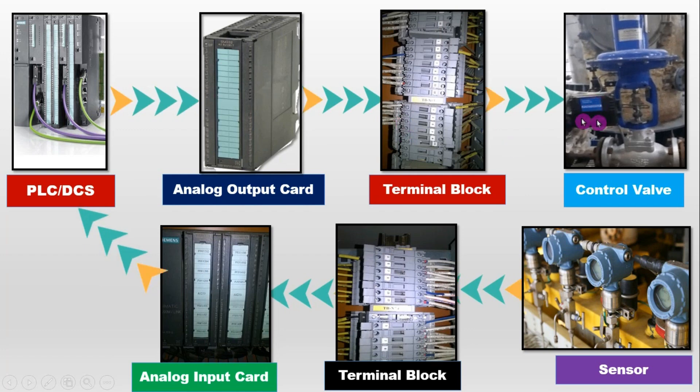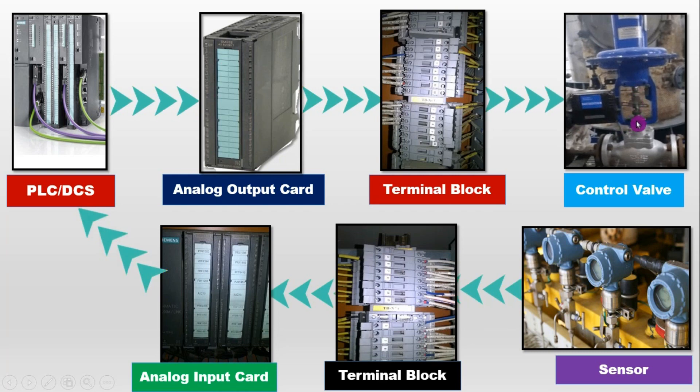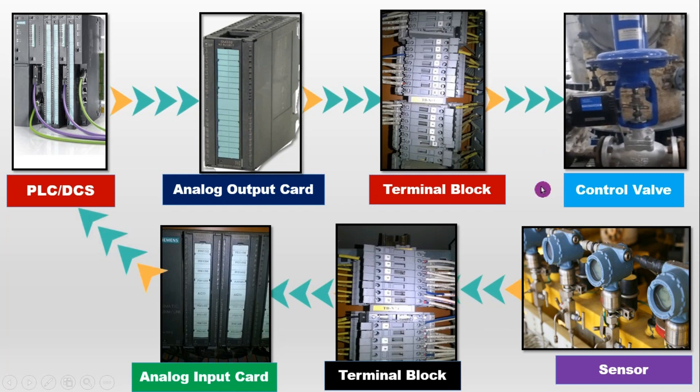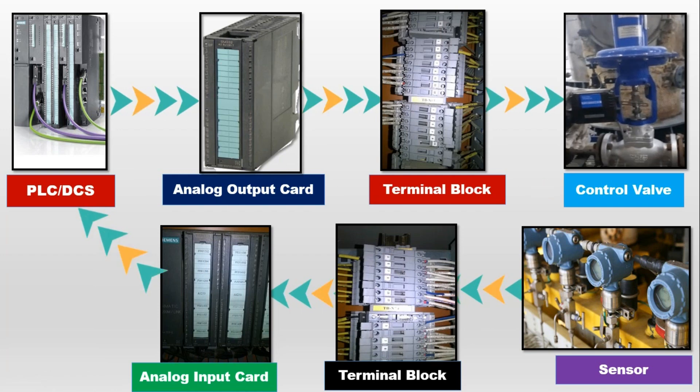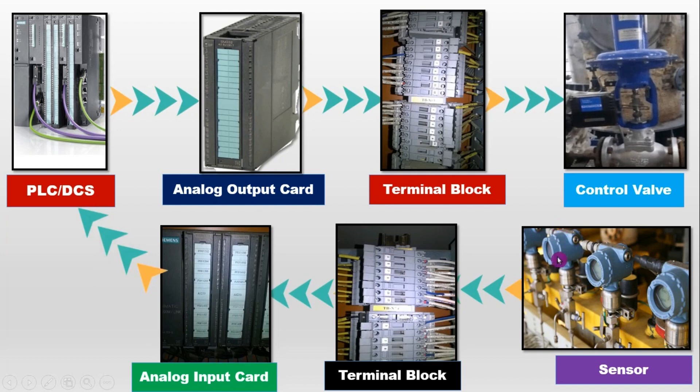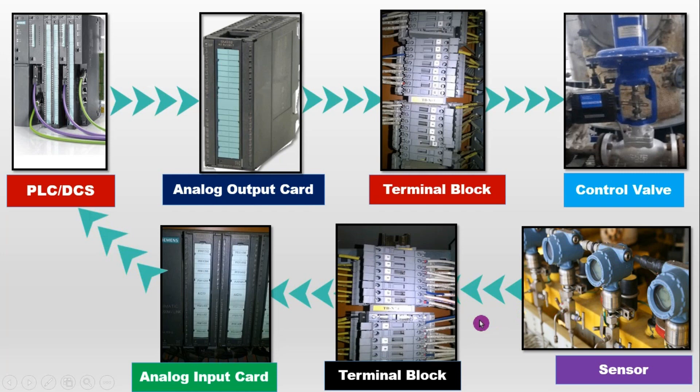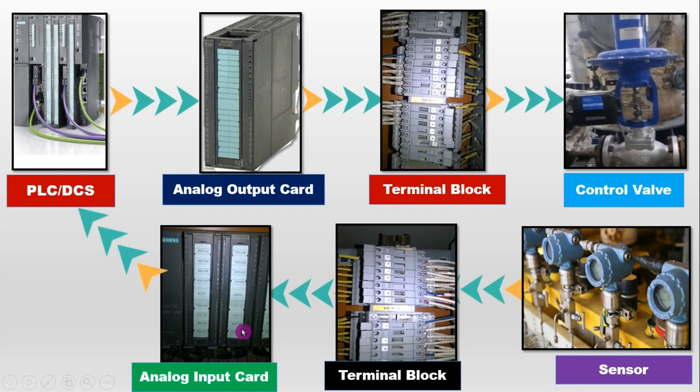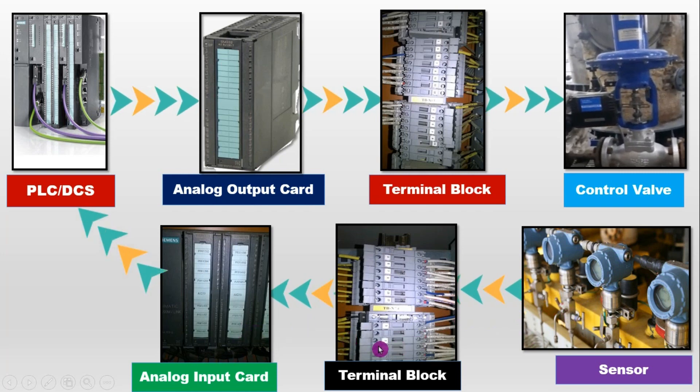When control valve operates, it maintains some parameters. Suppose it is maintaining the pressure. The measured signal, or we can say the measured pressure from sensor, is sent to analog input module in PLC DCS panel via terminal block. Analog input module sends this feedback signal to PLC DCS.